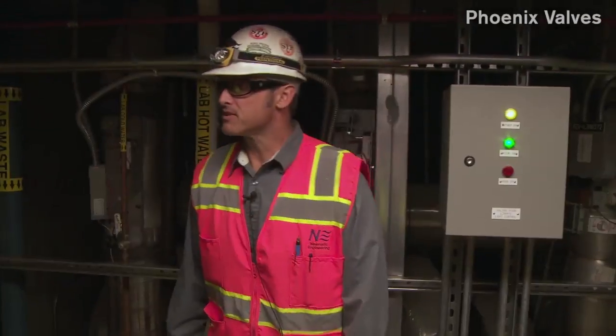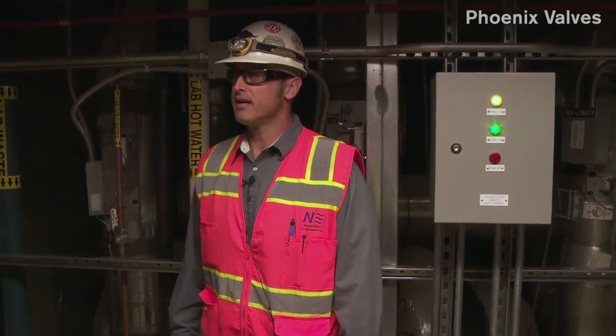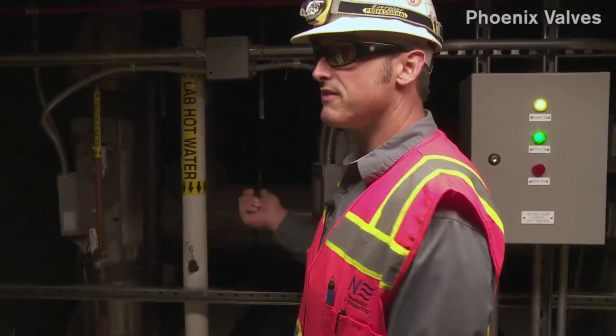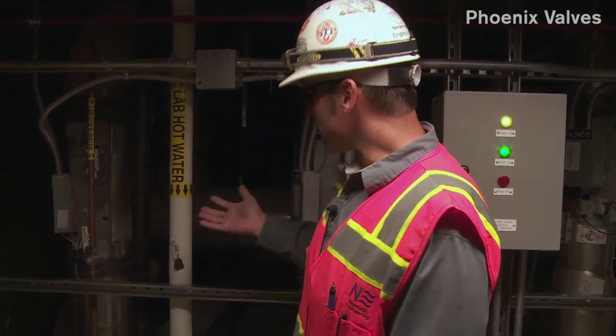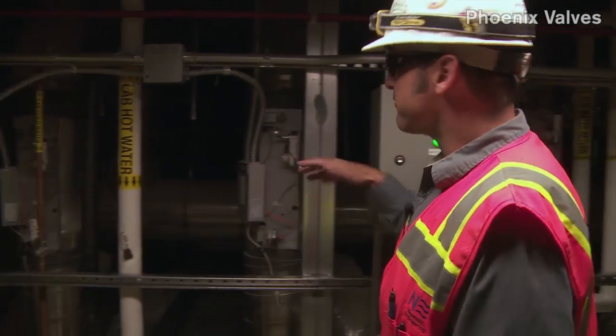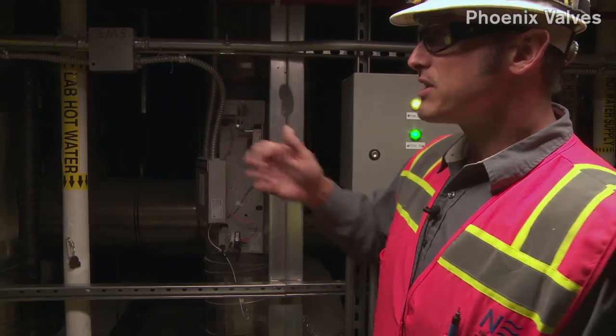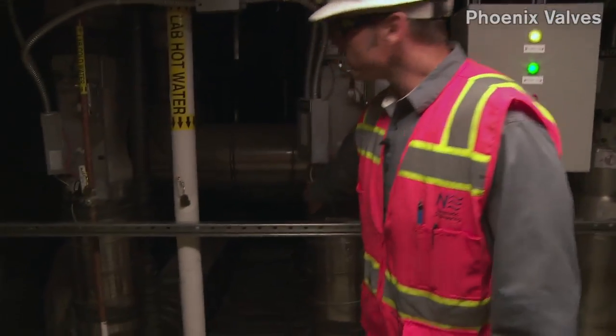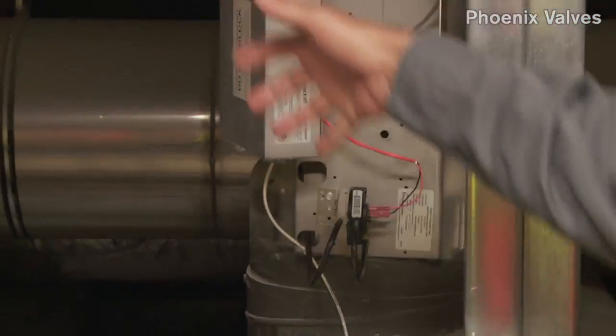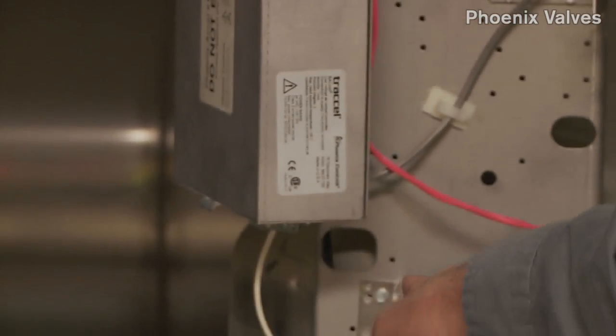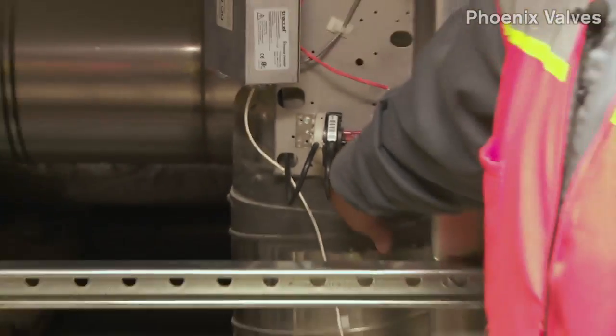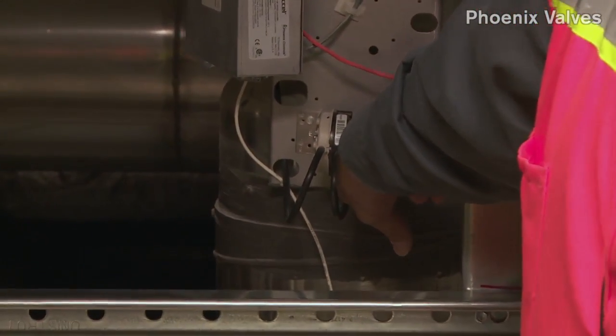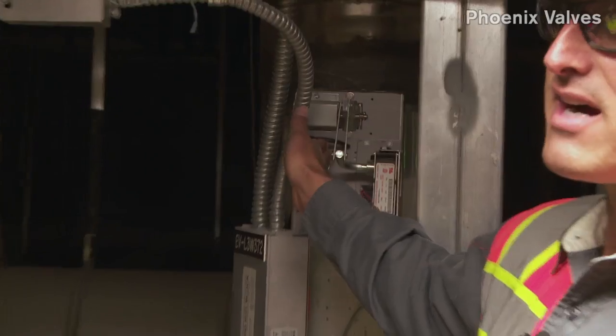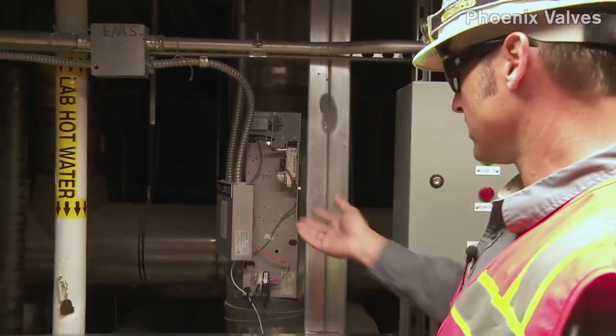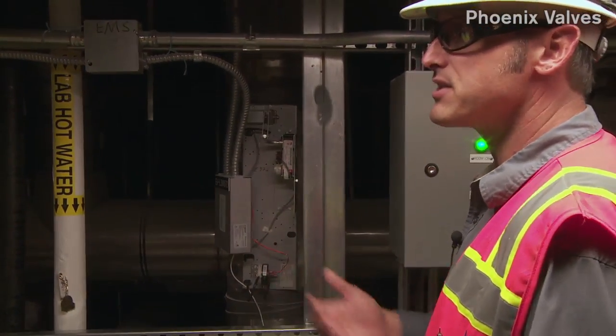All right. My name is Don Tilsky. I'm with Nematic Engineering, and we're just going to talk about the valves that we have in the vivarium interstitial catwalk area. We have 3 different types of valves here, the ones that Rich was pointing out. We have a general exhaust valve that looks like the spun aluminum valve itself. These down here have a pressure switch with pneumatic polytubing on either side of the valve. That's what tells the valve if it has the correct differential pressure across it.